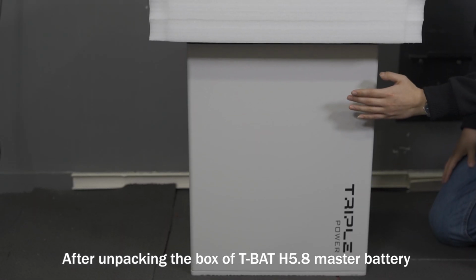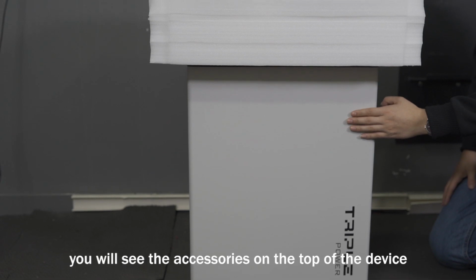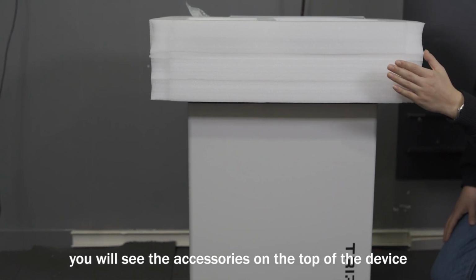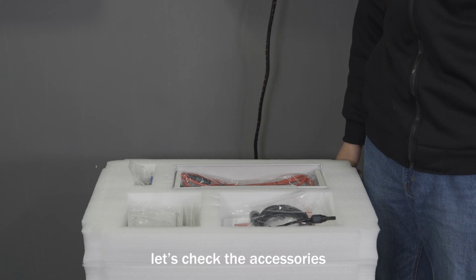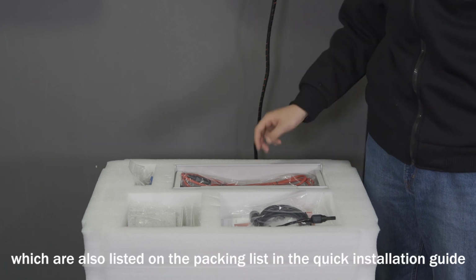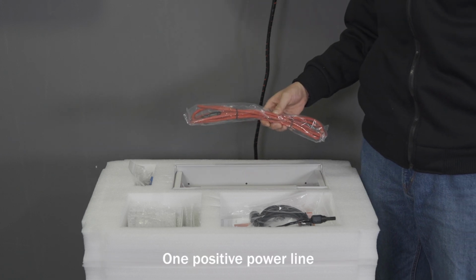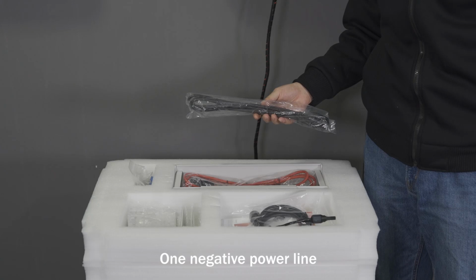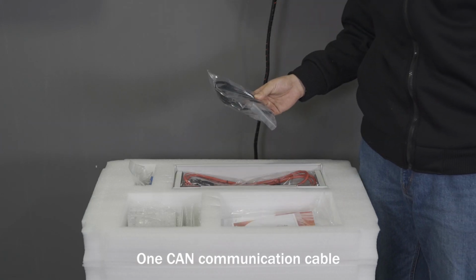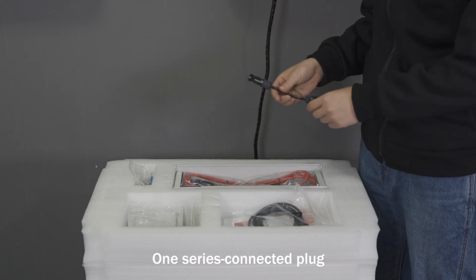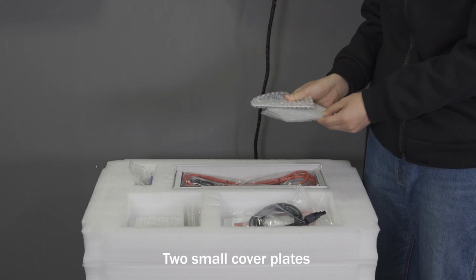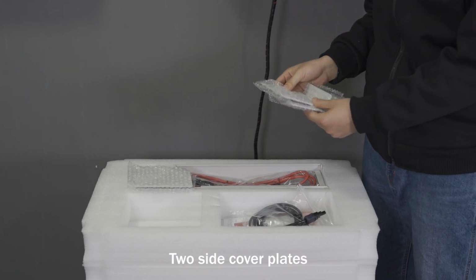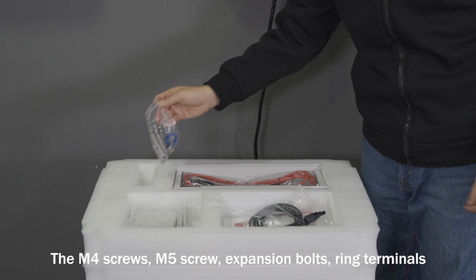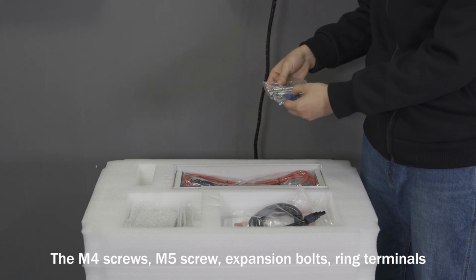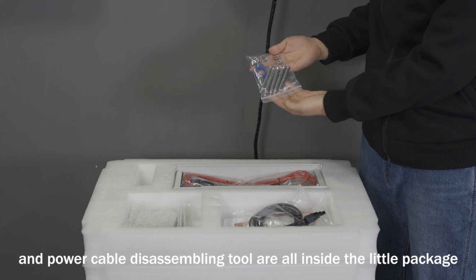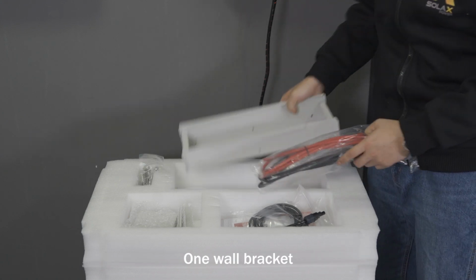After unpacking the box of T-Bat H5.8 master battery, you will see the accessories on the top of the device. First, let's check the accessories, which are also listed on the packing list in the quick installation guide. 1 positive power line, 1 negative power line, 1 CAN communication cable, 1 series connected plug, 2 small cover plates, 2 side cover plates, the M4 screws, M5 screw, expansion bolts, ring terminals, and power cable disassembling tool are all inside the little package.